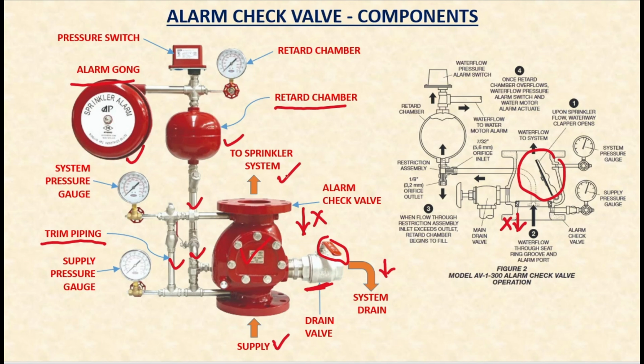So next let us see this part actually. See the pressure switch actually. This pressure switch is basically an electrical device. This one is basically an electrical device actually, which is called a pressure switch. This pressure switch is designed to detect change in water pressure within the fire sprinkler system. Upon detecting a pressure drop, the pressure switch sends a signal to the fire alarm control panel. So this activates local and remote alarms to notify occupants.